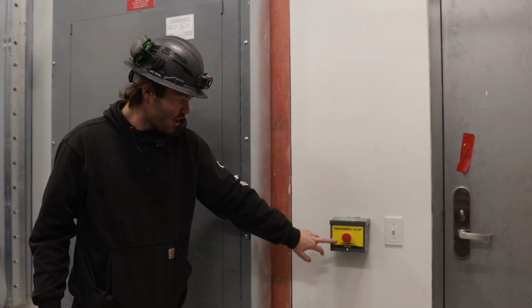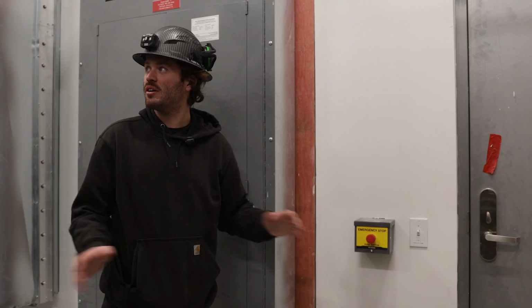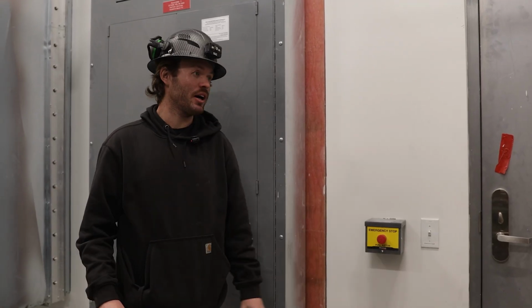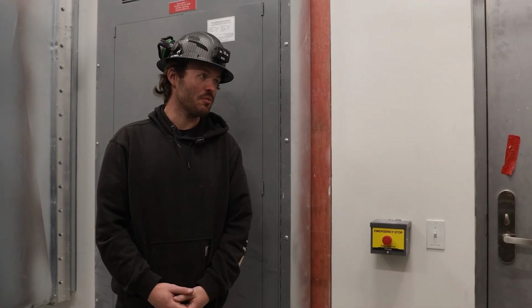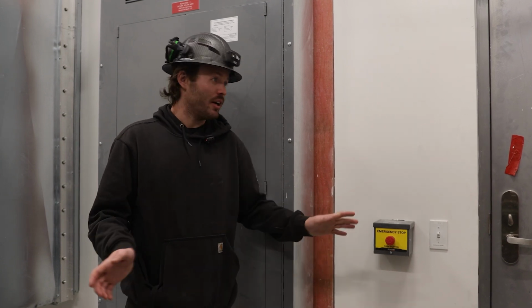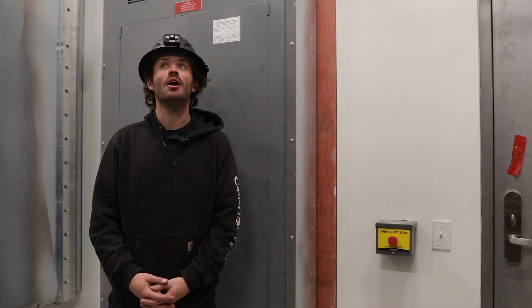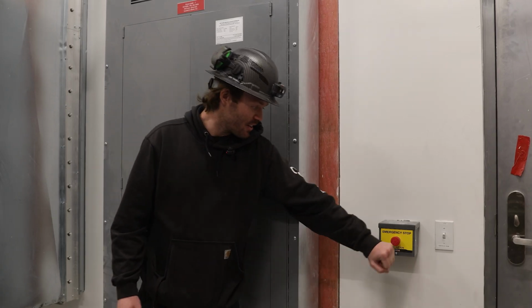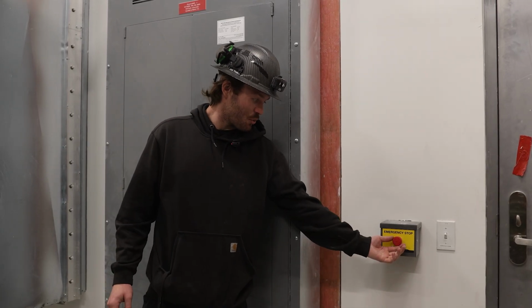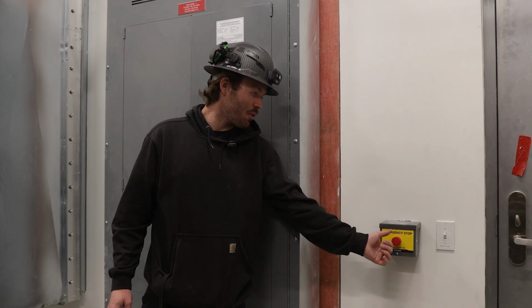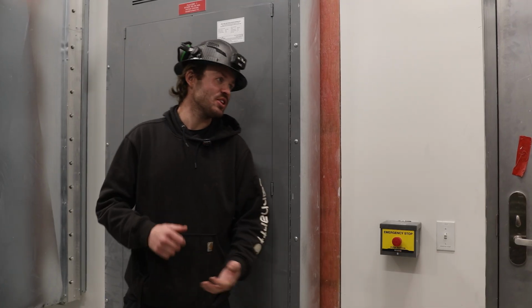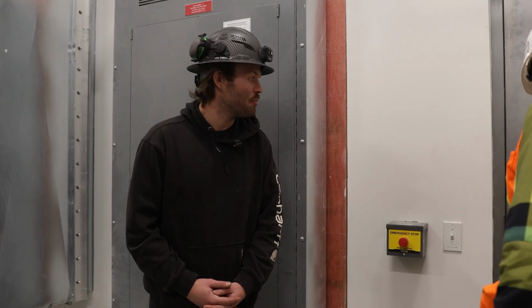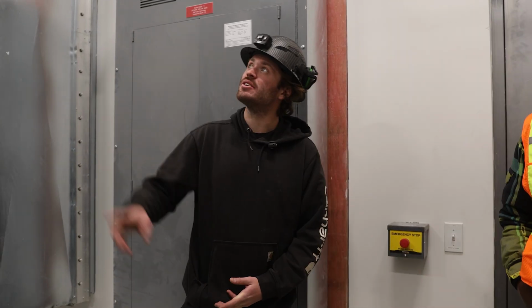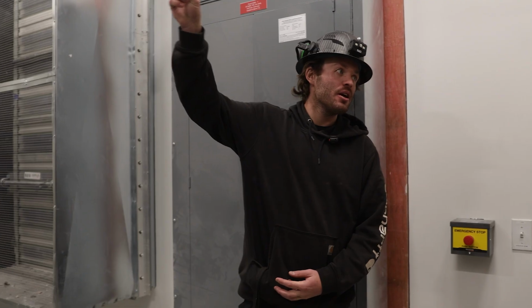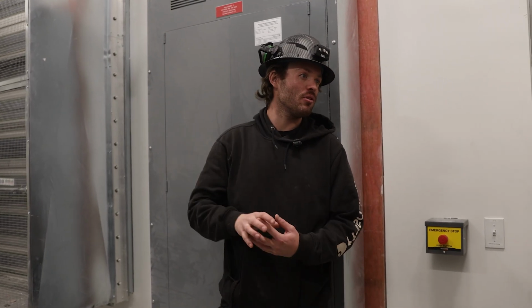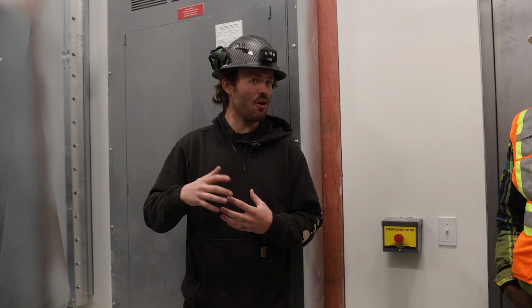Beside it, emergency stop for the generator. So if you're in here and something's going wrong, you slap that without having to run all the way around the generator to the opposite side. Slap it, close the door, get out. To reset the emergency stop, it's a twist. Give it a slight twist, it'll pop out. Then go back over to the generator and reset the fault on the generator. Yeah, that's probably been beeping this whole time. There's a combustion air fan up in the room. You hear it running right now. That fan will always be running. It's always drawing air out or in the room.